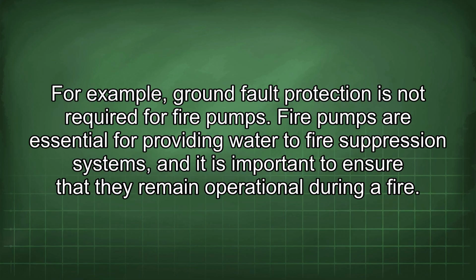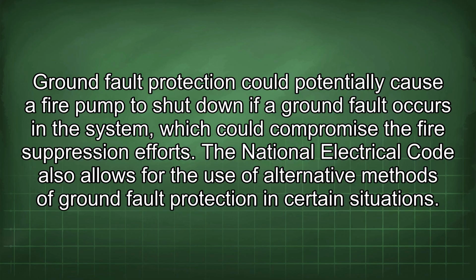Fire pumps are essential for providing water to fire suppression systems, and it is important to ensure that they remain operational during a fire. Ground fault protection could potentially cause a fire pump to shut down if a ground fault occurs in the system, which could compromise the fire suppression efforts. The National Electrical Code also allows for the use of alternative methods of ground fault protection in certain situations.